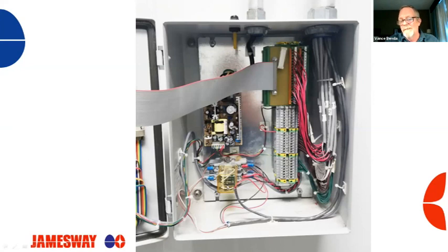And this relay, when this alarms, is going to de-energize. So what this customer does is hook the 12-volt power supply. We have 12-volt standing by on this side of the relay, hooked to normally closed contacts. So when the relay's energized, the contacts that we're hooked to are open, and this is your horn over here, so nothing happens. As soon as this alarm occurs, this relay is going to de-energize. You're hooked to normally closed contacts, so you're going to sound a horn.